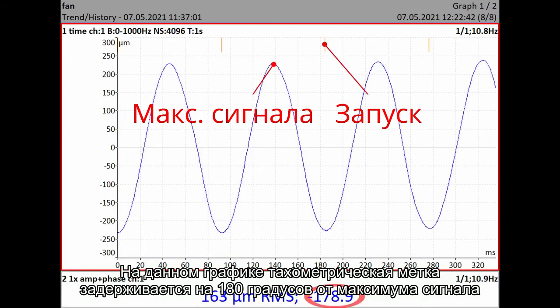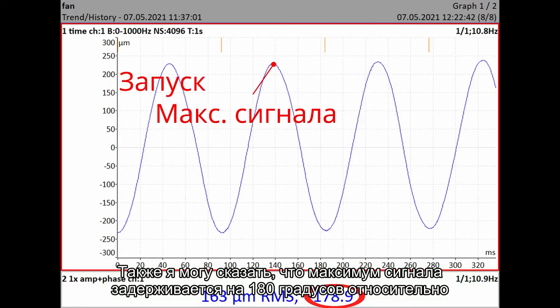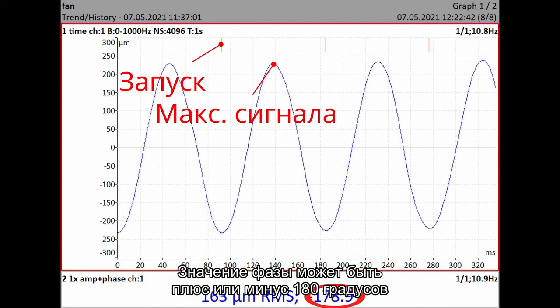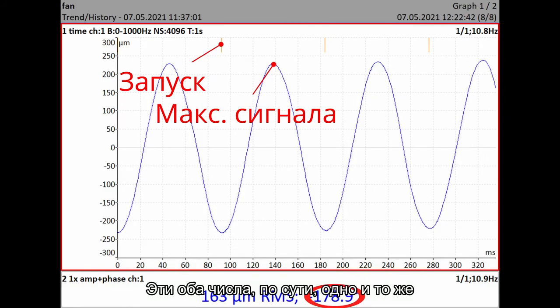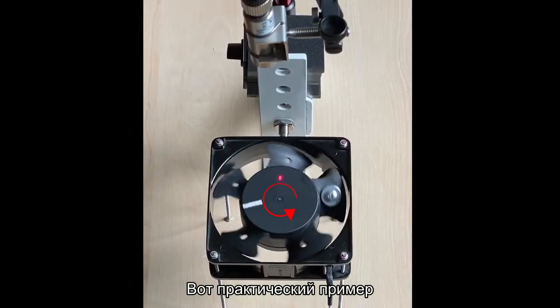In this graph the tacho mark is delayed by 180 degrees from signal maximum. But I can say that the signal maximum is delayed by 180 degrees from tacho mark. The phase value can be plus or minus 180 degrees. These both numbers are the same. Here is the practice example.